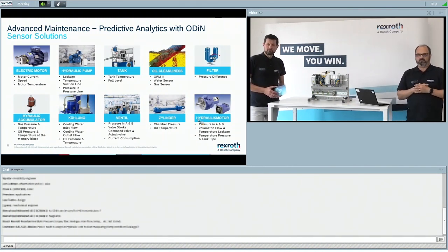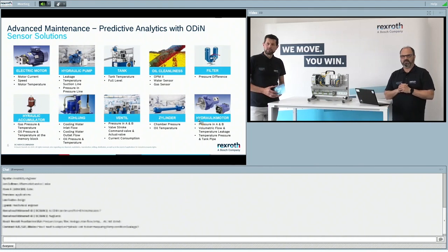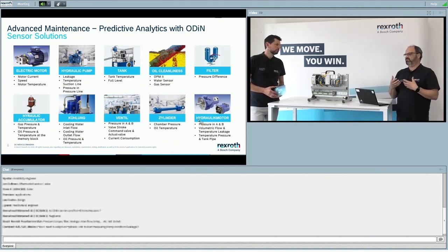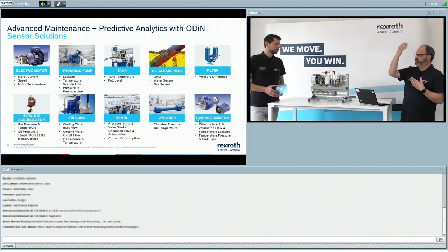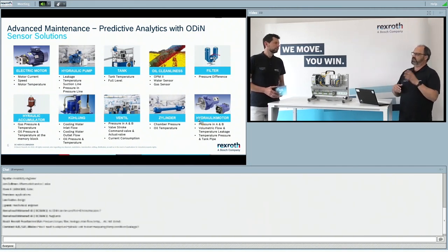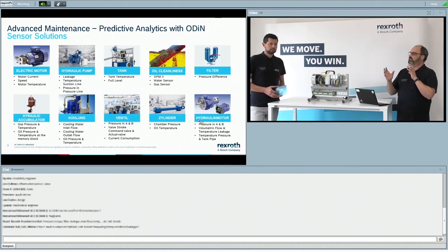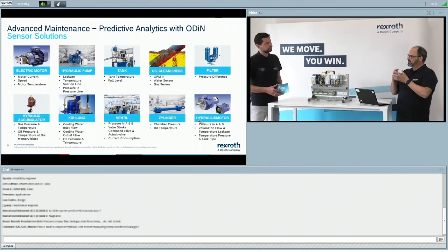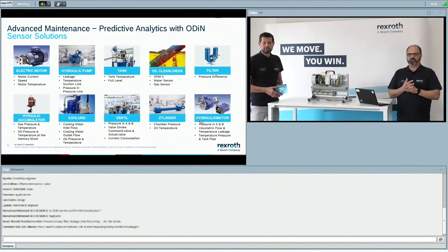A question from Mexico: how can I adapt the hydraulic unit to start measuring pump condition? We measure leakage in the drain line, together with temperature. With these three physical measurements — pressure, leakage, and temperature — we can tell from the hydraulic side whether the pump has a problem. Together with the motor current, we can also determine if the issue is mechanical.